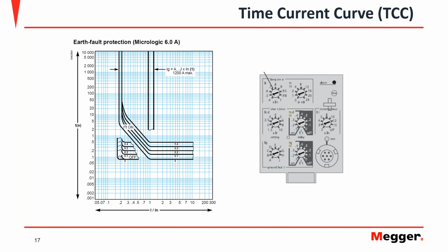Thanks, Jason. And while I have you, if the main breaker is connected to a utility transformer, does it need to be disconnected from the main breaker in order to do the GF test? Well, the short answer to this is no, it doesn't. As some of the examples that Daniel gave when he was showing how to connect the test set, all you really need to do is to connect the device in that manner and ensure that the current flow you have while you're performing the primary injection across that system is applied properly.